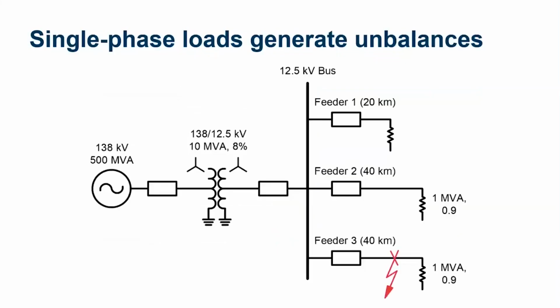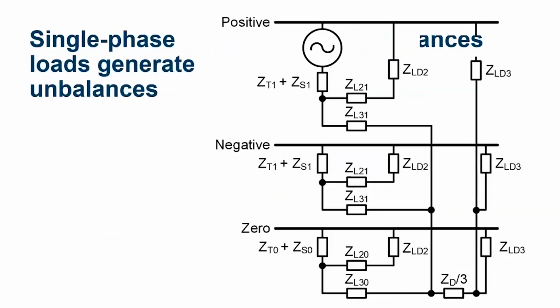And so here's an example power system. We have a few feeders here, and in this case, we are looking at a potential fault on feeder number 3. On this feeder, we have an imbalance of our loading. Our single phase loads are not typically balanced perfectly, or we can also have the case where we have to plan for contingencies of a large single phase outage on a large single phase lateral. Say we blow the fuse on a large single phase branch or lateral, and now we have this imbalance. We can see this imbalance is going to appear in our zero sequence circuit right here, and we're going to have standing zero sequence current.